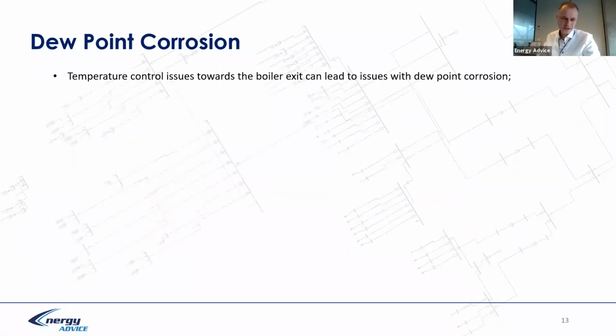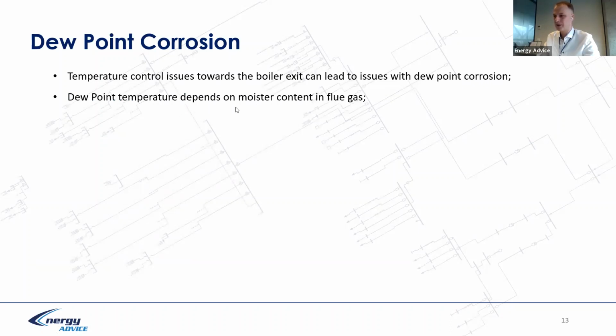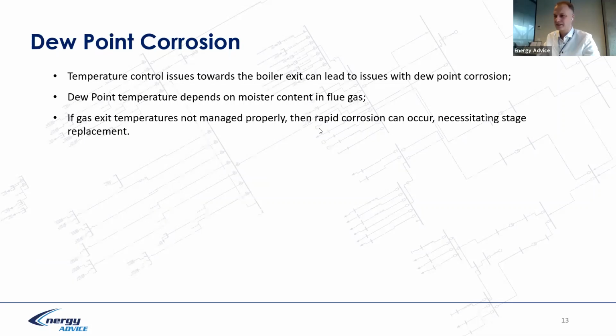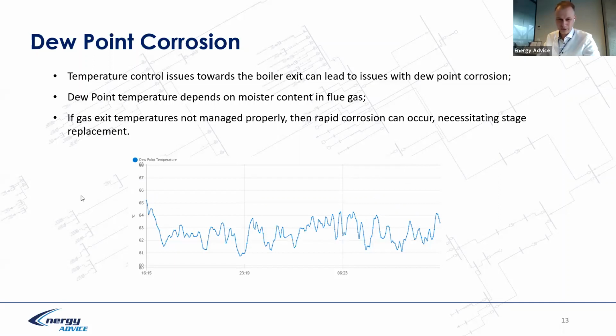Dew point corrosion is another type of corrosion. Of course, we have control issues. Boiler exit conditions can lead to dew point corrosion, and dew point temperature depends on the moisture content in the flue gas. If the gas exit temperature is not managed properly, rapid corrosion occurs, necessitating stage replacement. So in our solution, we calculate the dew point temperature of the flue gas every 5 minutes, like a digital twin.